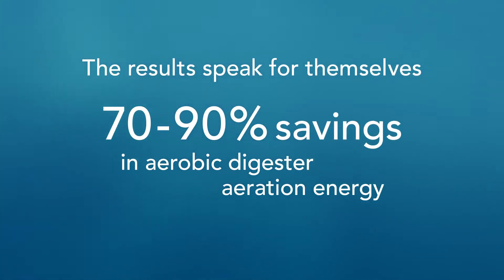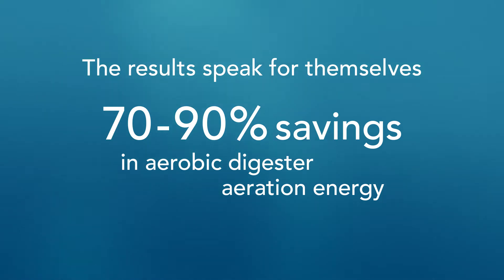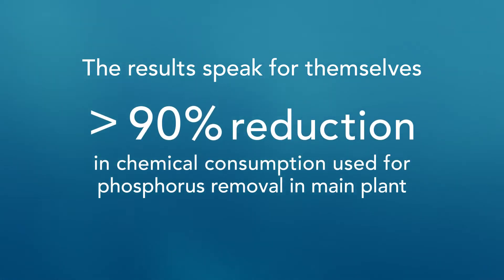The results speak for themselves. Between 70 to 90% savings in aeration energy, depending on loading rates. Greater than 90% reduction in phosphate returned to the main treatment plant. Greater than 90% reduction in the chemical consumption used for phosphorus removal in the main plant. And much more stable effluent, with far fewer occurrences of potential effluent permit violations.